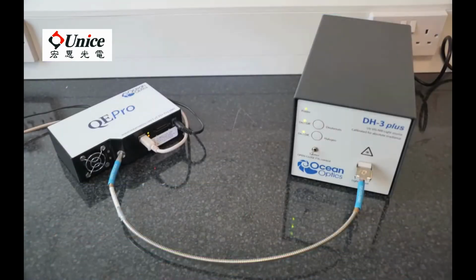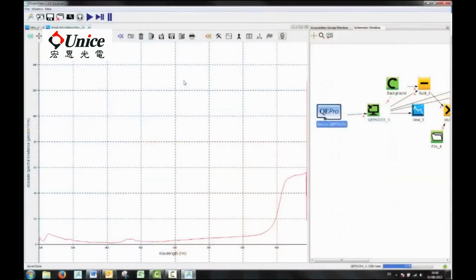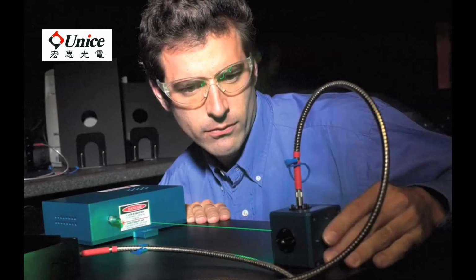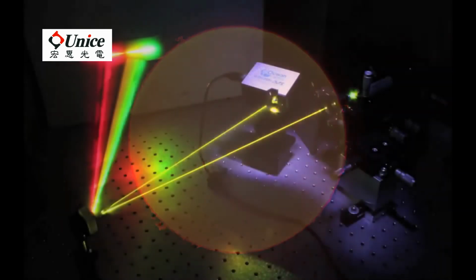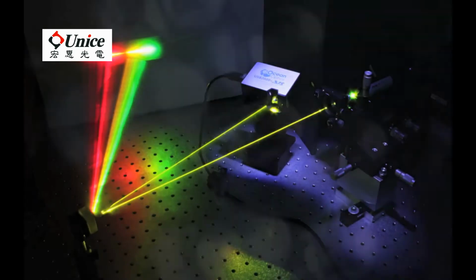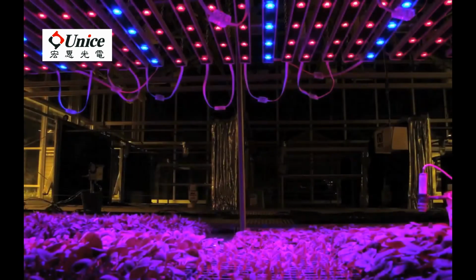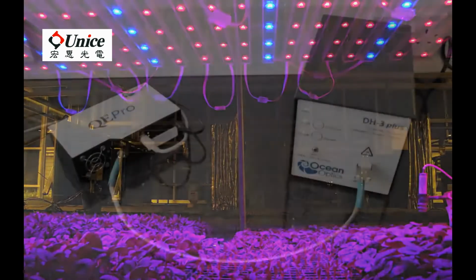This video will demonstrate how to take measurements that are calibrated for absolute irradiance using Ocean Optics equipment. An absolute irradiance calibration can be essential when performing measurements that need to relate to absolute values. The absolute irradiance data can be compared with any other absolute irradiance measurements and removes the individual response of the system that you are using.